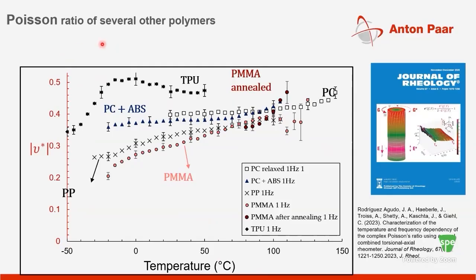So having a combined axial torsional type device really opens up new experimentation for folks, and this could have significant implications, right? Especially for people who work in the simulation groups and who are doing FEM, or finite element type simulations and modeling. Most times they need data on Poisson ratio to model systems, and typically there is no data, as I said earlier, or very scarce data is available. So really measuring it helps in that case.